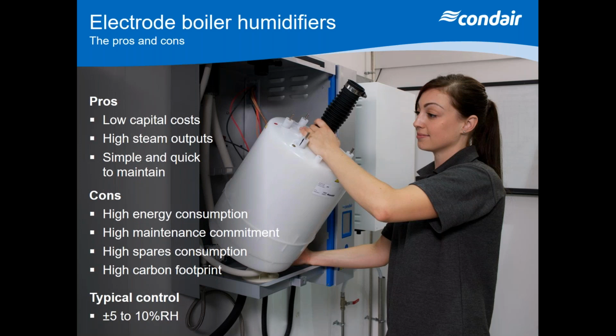The basic principle of it is that you're going to have a polypropylene cylinder, which will have a number of electrodes fixed inside the cylinder itself. That can either be fed by a single-phase supply or a three-phase supply. And those electrodes can either be in the form of a mild steel mesh plate, or a stainless steel plate, depending on which manufacturer you're using.